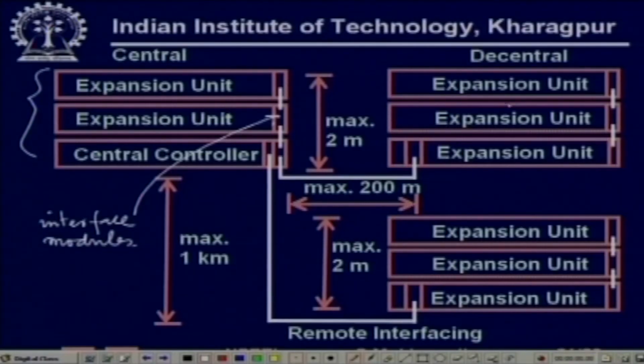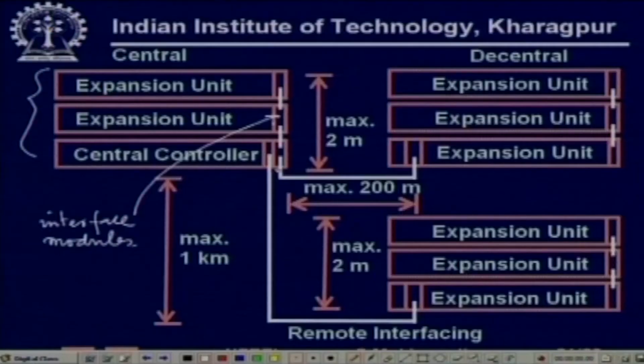Sometimes, as I was telling, you can put your modules in a different almirah, which is a different cabinet. When I say almirah, actually it is a cabinet. For that you need a special interface unit. Typically, for reliable data transmission at a certain rate, there are distance requirements, and you can go up to something like 100 meters, which is a lot.